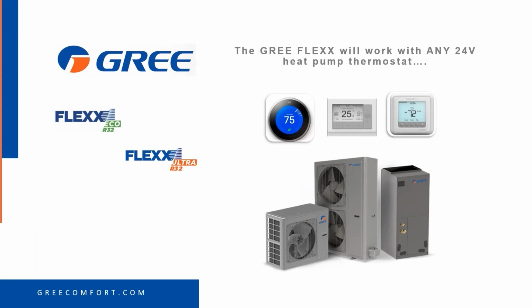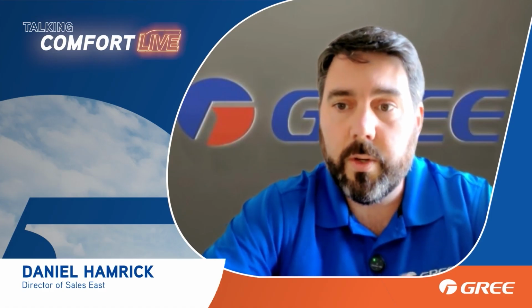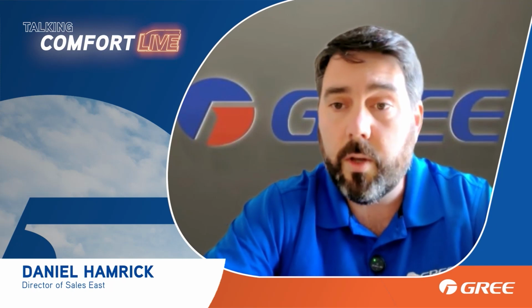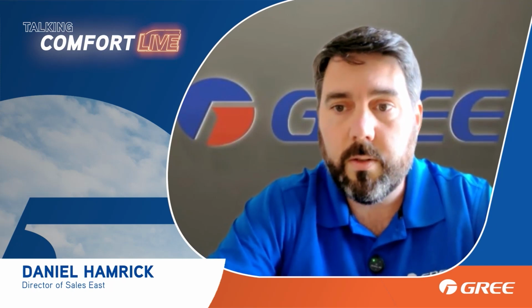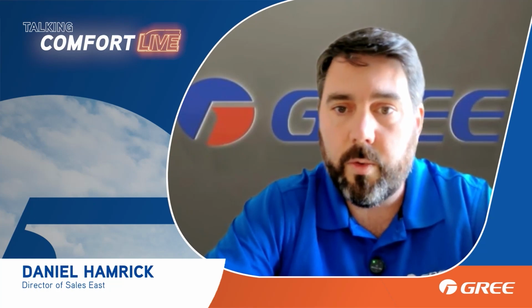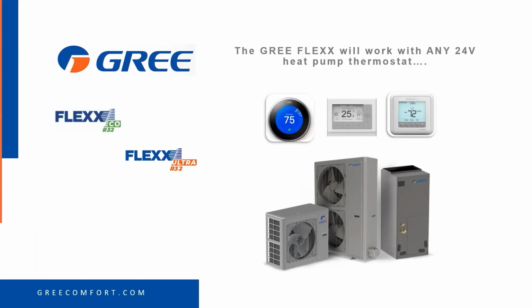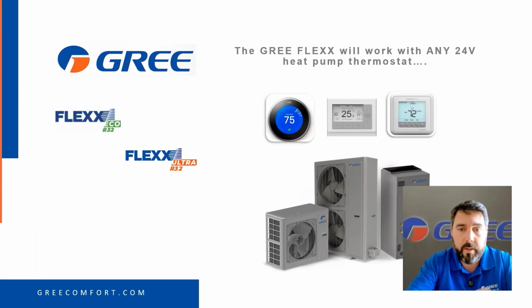The GREE FLEXX, like we all know, will work with any 24-volt heat pump thermostat. The addition is that now the air handler will be coming with the GREE controller. Now, if you choose to use true communication with this system, and we'll talk about how that works in just a minute, this GREE controller will allow you to have all the modes that your mini split does. So you'll have auto mode, you'll have dry mode, et cetera. If you choose to use it just straight 24 volts, you can choose whatever brand of thermostat that your homeowner or you prefer, Ecobee, Honeywell, any of those.